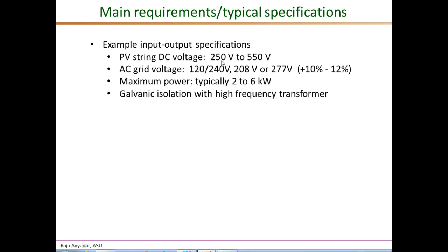Typically, this can be between 250 volts to about 550 volts. On the AC side, the PV inverters interface to the grid at either 120-240 volts. For example, in most residences in the US, the power is supplied through a three-wire 120-240 volt system, and the PV inverters connect directly to the 240 volt terminals.